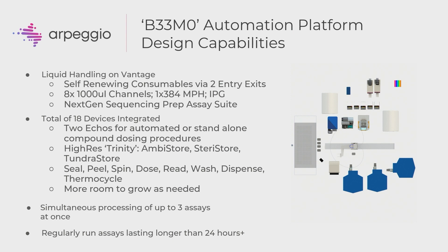Functions include seal, peel, spin, dose, read, wash, dispense, and thermocycle — with room to grow. One key capability is simultaneous processing of up to three assays at once: the same assay on different Echos, dosing and assaying at the same time, as well as auxiliary functions like sealing or treating plates simultaneously. One thing I'm proud of is we can run this thing for over 24 hours — we're getting to the point where we can run it for 30 to 36 hours regularly. It's pretty commonplace for people to kick off runs on Friday afternoon and come back Monday to just clean it up.